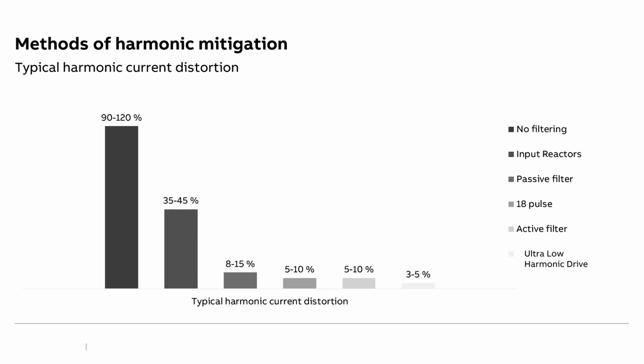There are passive filters of 5% and 10%, and similarly, in active filters, we have 5% or 10% filters. Those are available in the market and we can utilize them. The difference between passive and active filters is this: if we are using a passive filter, it needs to be installed with each VFD. However, if we are using an active filter, we can design one common active filter at the PCC, which will take care of all the harmonics inside the system. This is the major difference.